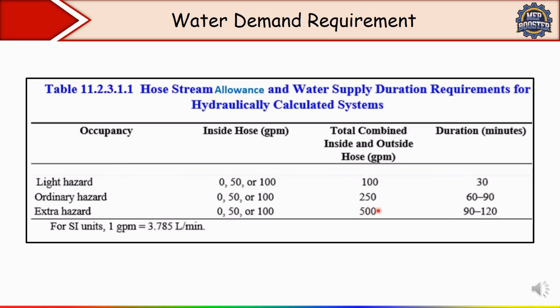Correct. Then here the duration is given. This is the minimum time for which the required water flow must be maintained. For light hazard 30 minutes, for ordinary 60 to 90 minutes, and for extra 90 to 120 minutes. Okay, so you need to remember this. The first thing you need to remember is what? The water demand increases with hazard level. If you see, higher risk areas like extra hazard need more water for a longer duration, you can see here.